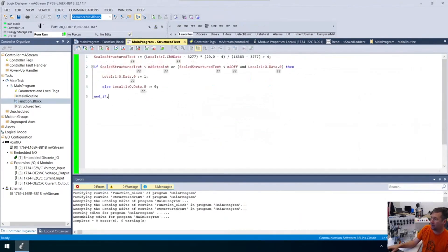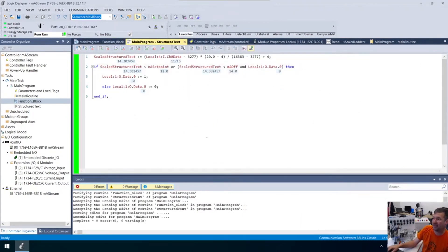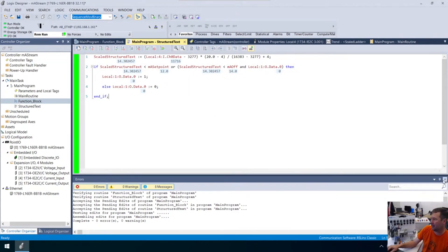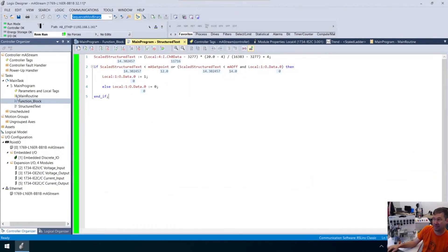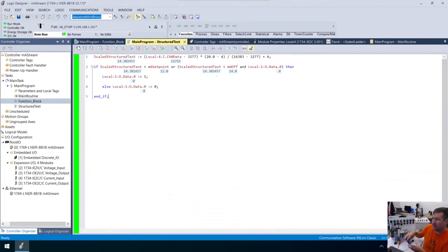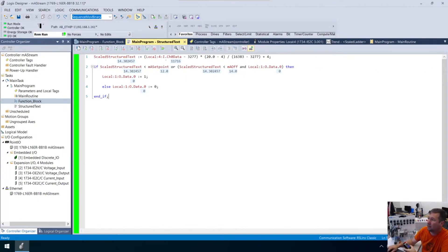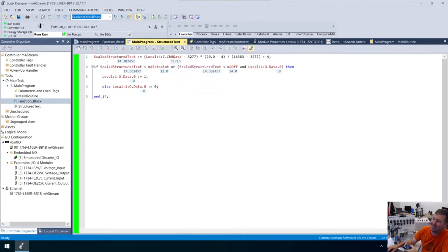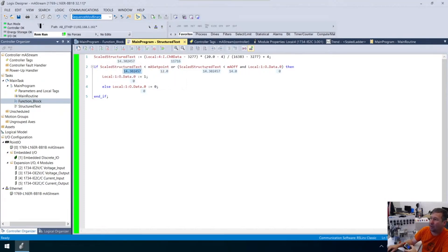All right. And now if we go to our structured text, and here's where we go. Notice that while I was editing, I couldn't see the values. And I think they made a good compromise. I wish this was the default value or maybe they just, I don't know. If you do not know that you can look at these values in structured text, it can be a nightmare to troubleshoot. But all right. We are at 14.3 milliamps. Uh-oh. What did I do wrong? I did something wrong here. Oh no. Okay. Here's our scaling. That's our scaling. Here's where we're at. 14.3 has to be less than 12 or 14.3 has to be less than 14 and our output be on.